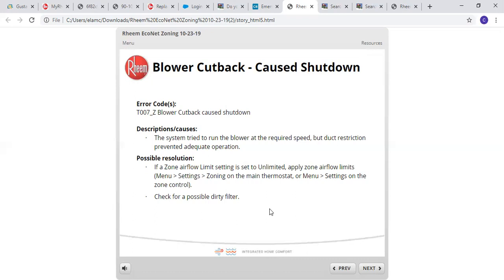These systems, as with all ECMs, they do not want to exceed 1 inch of static pressure. So if you look there and you see 1.25, okay, you know you have some static pressure issues. Your duct's too small, either on the supply or the return. If you look on there and it says unlimited or unknown, that means it's so far out of whack that the blower cannot even determine what the static pressure is. If you do indeed have that, then you have to dig into your duct system and find the culprit, whether it's supply or return, and get that resolved.